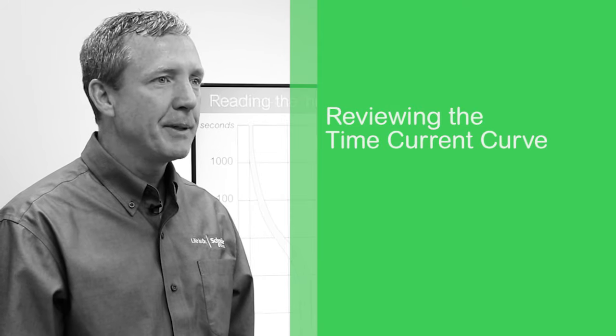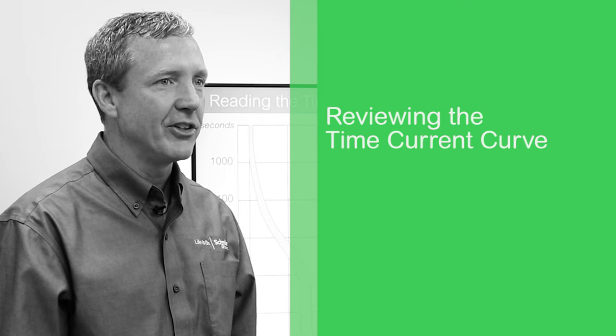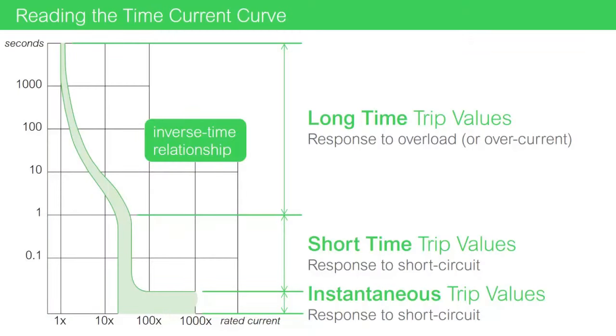In review, to be able to identify ranges and values, remember that for a time-current curve, you need to know the amperage rating of the circuit breaker to understand what the multiple rated values of the circuit breaker would be. Remember that the trip responses have a trend of an inverse time relationship. The higher the current, the faster the response.